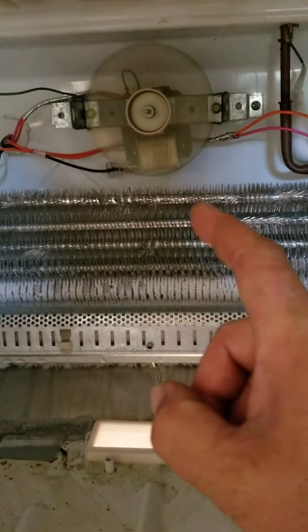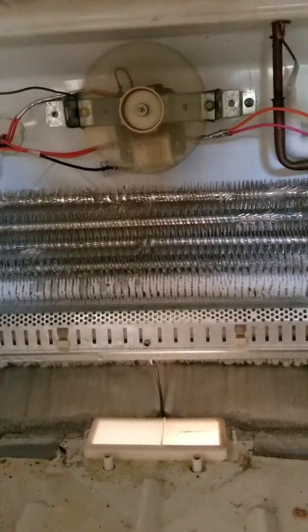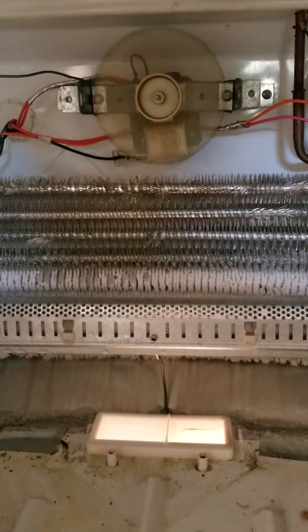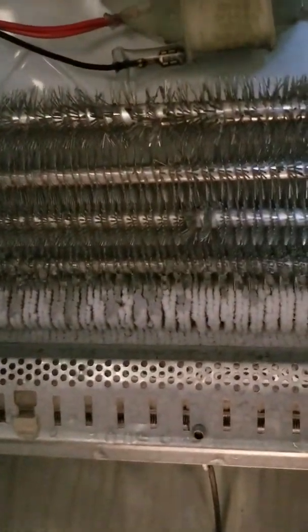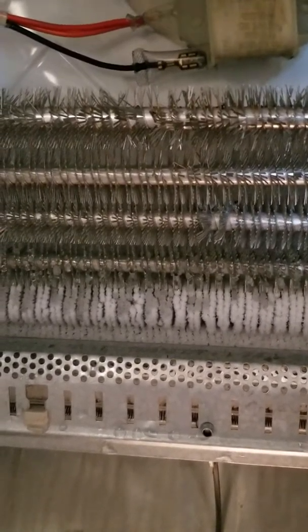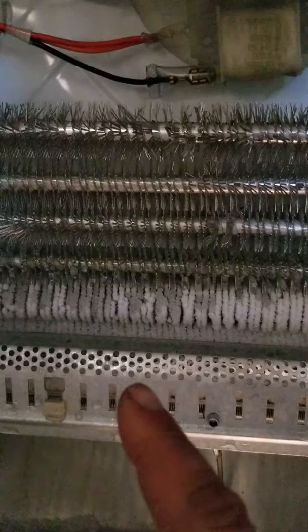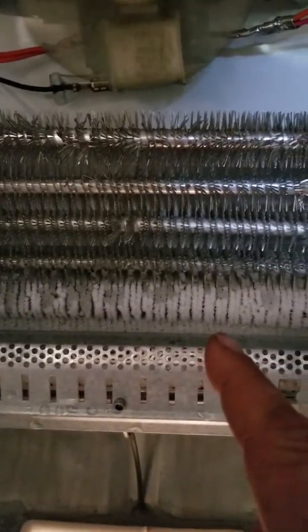This evaporator fan — motor is going out. I was able to kick-start it, but I'm going to have to replace that. If you look closely, you can see that the defrost timer is working, so it's good.